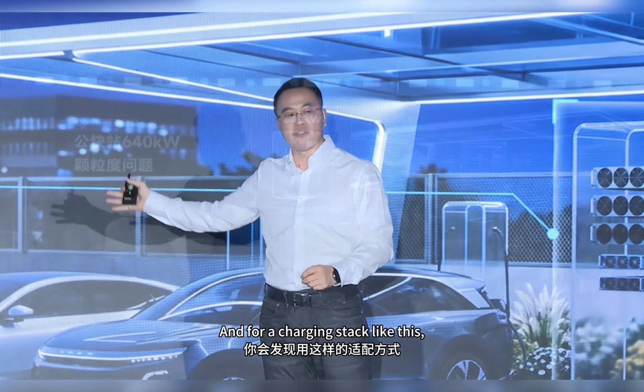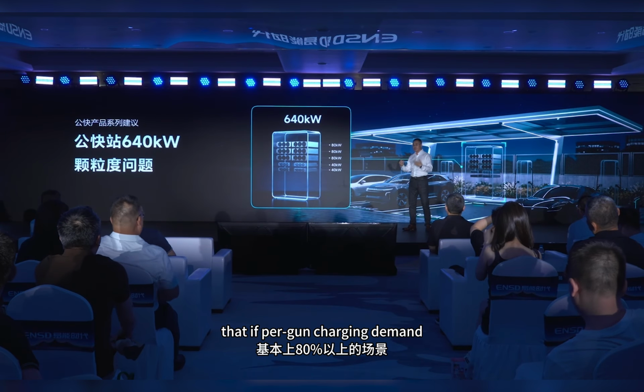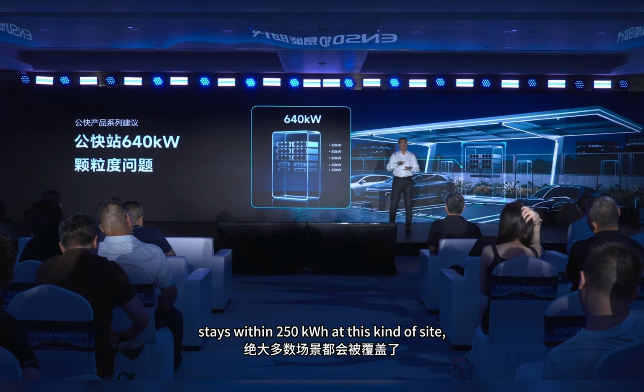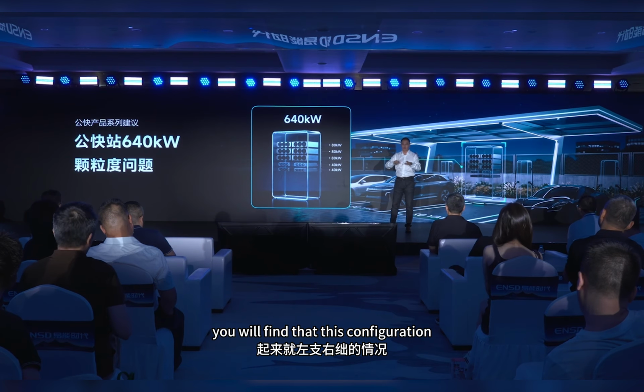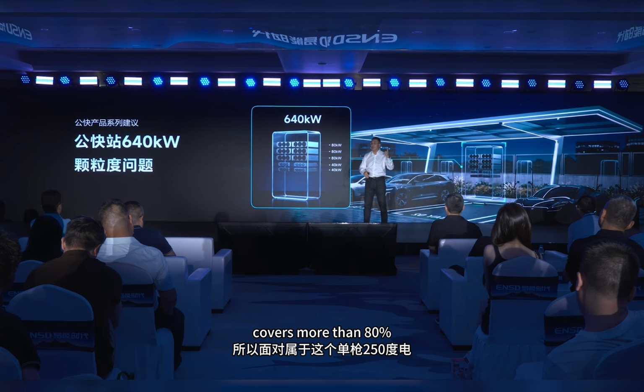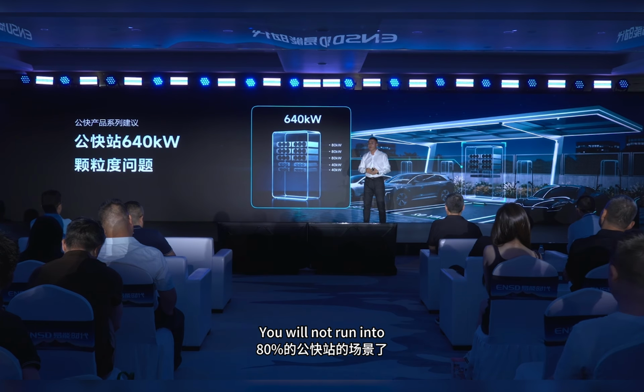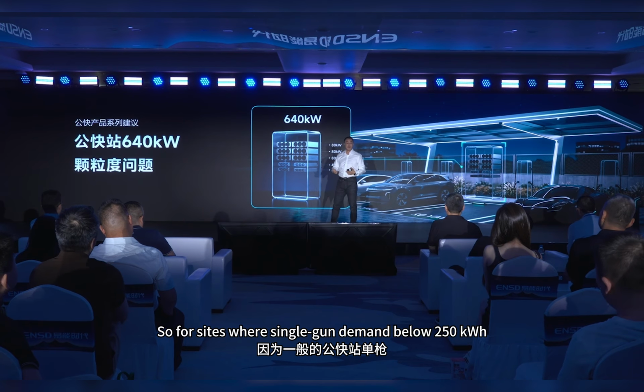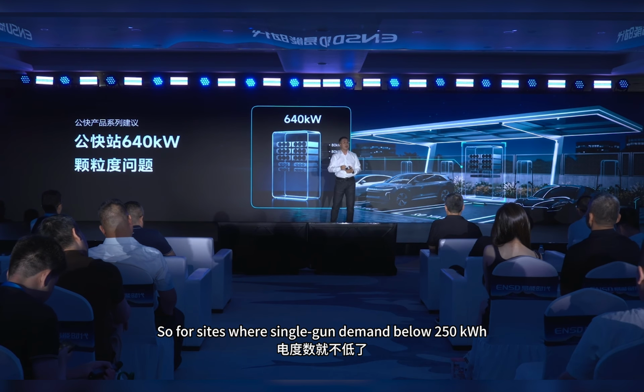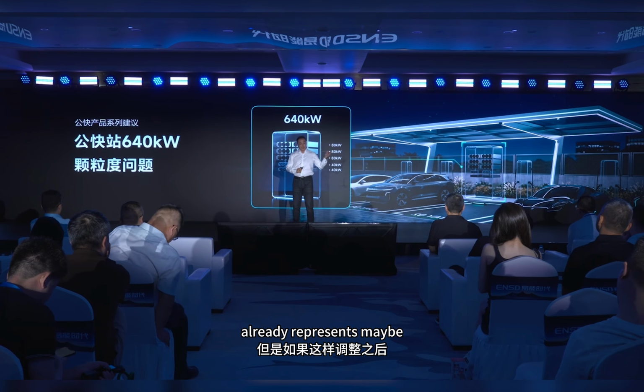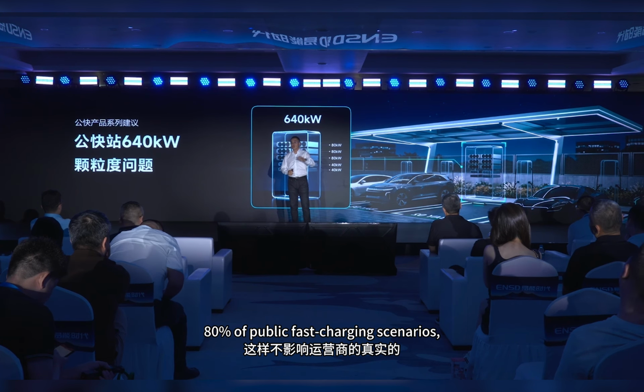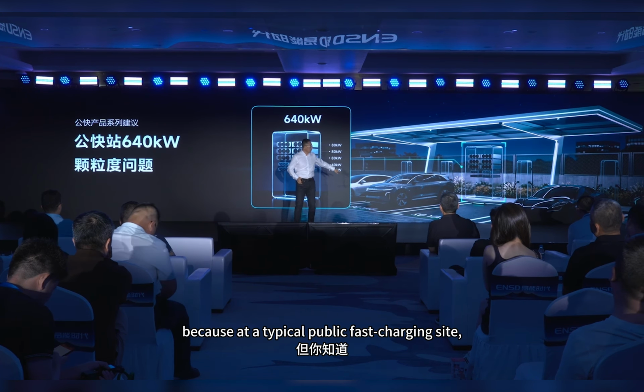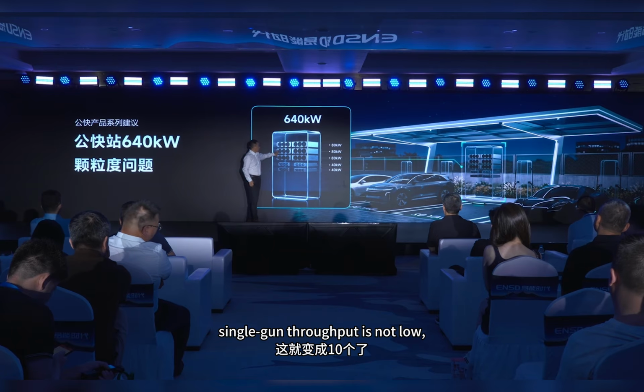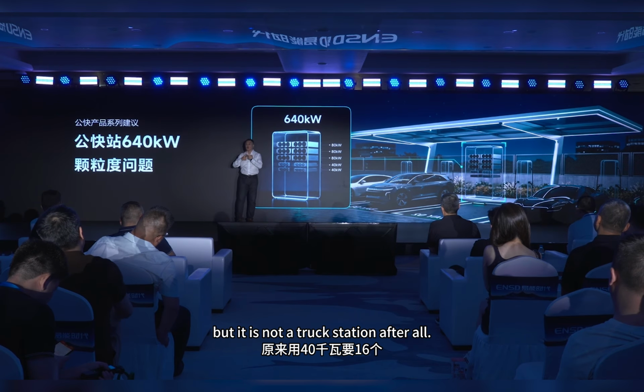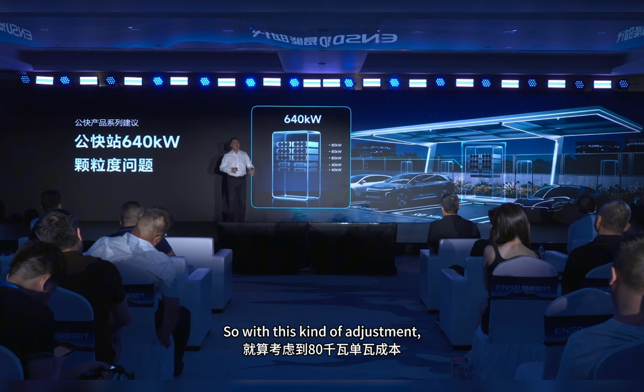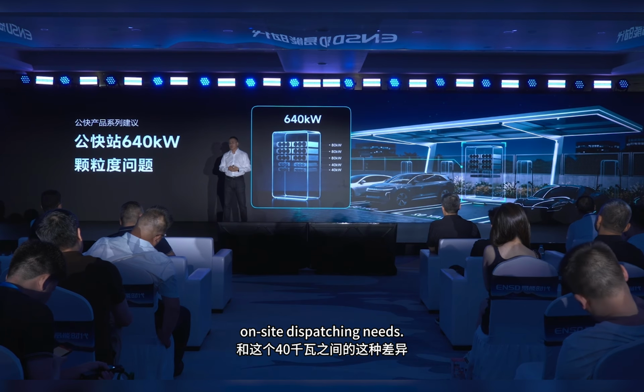And for a charging stack like this, our rough calculations show that if per gun charging demand stays within 250 kilowatt hours at this kind of site, this configuration covers more than 80% of typical scenarios. You will not run into dispatching bottlenecks. For sites where single gun demand below 250 kilowatt hours already represents maybe 80% of public fast charging scenarios, because at a typical public fast charging site, single gun throughput is not low, but it is not a truck station after all. So with this kind of adjustment, it does not affect the operator's real on-site dispatching needs.